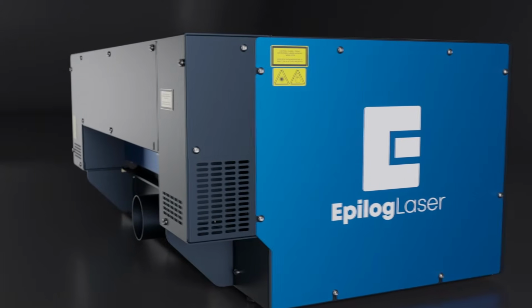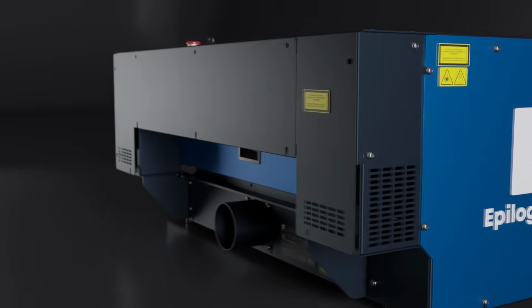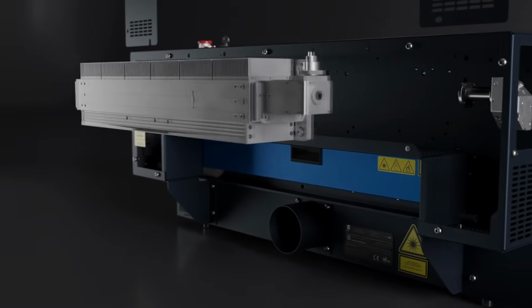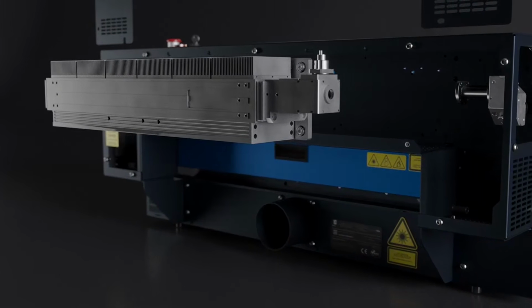That's great. So it's a metal ceramic design. Why does Epilog go with that kind of design? Yeah, so we have a ceramic and metal structure inside the laser, and then around that we chose to use a metal vacuum container or vessel. The reason for that is because the methods for joining metal to metal, welding, sometimes adhesive, all of those things are pretty well known in the industry and well established. Joining 2 pieces of ceramic together is tough, and the parts are expensive. So if that doesn't go as planned, it can be a very challenging thing for production.